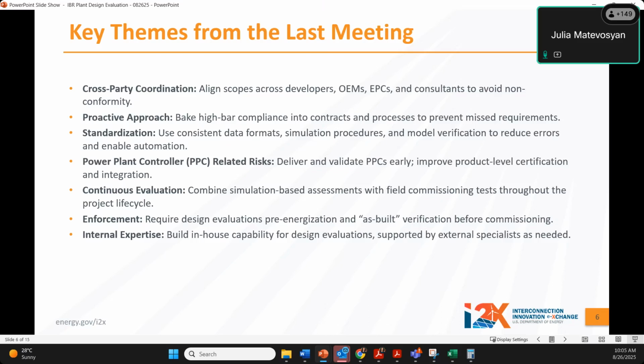There needs to be continuous evaluation—it's not a one and done kind of thing. Design evaluation needs to combine simulation-based assessments with field commissioning tests throughout the entire project development cycle, and also the lifetime of the project, to make sure any changes in design are reflected in the models, studied as needed, and all impacts are captured.